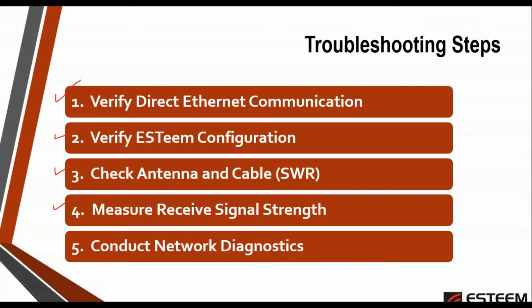What this does is verify that we're actually receiving the information we originally started with, because the problem may not necessarily be at the site showing the problem. It may be at the site this one is communicating to. If we verify the signal strength hasn't changed, we can run data over the top of it. This may be as simple as a ping test between the computer plugged into that radio and the other radio, or a connected device to it, just verifying those two radios are exchanging information. If all of that looks good, the problem is not in the radio system, and we need to continue troubleshooting outside of it.